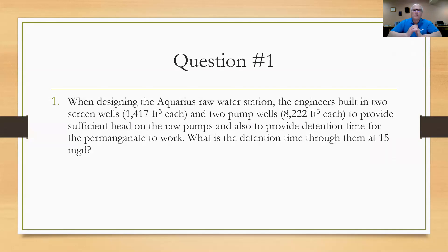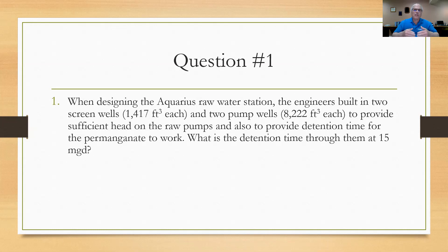Question number one: When designing the Aquarius raw water station, the engineers built in two screen wells and two pump wells. You see the volume of each, to provide sufficient head on the raw water pumps and to provide detention time for the permanganate to work. The Aquarius plant has a remote raw water station that sits right on Lake Erie. Water comes in from the intake and before the screens you're able to add potassium permanganate. Each screen well is 1,417 cubic feet and each pump well is 8,222 cubic feet. What is the detention time through them at 15 MGD?